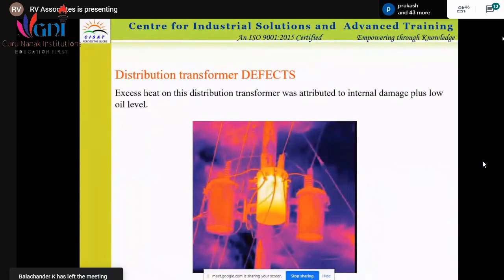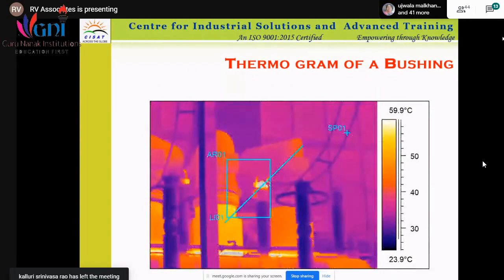This is a picture of a distribution transformer. See that one of the phases is getting heated. Why is it getting heated? That is to be again analyzed. Bushing: here one bushing is getting heated. Again, what is the reason? The reason can be that the brazing is not proper. There may be a loose connection. How does that loose connection happen? It may be because a particular maintenance employee who was doing the maintenance of the bushing, while fitting or refitting, has not tightened the screw properly. So that can be the reason.